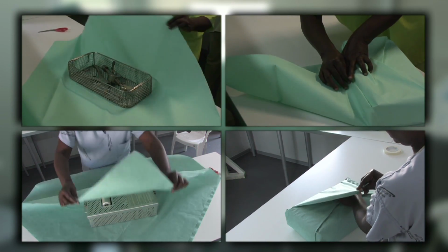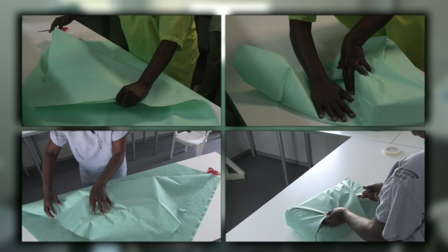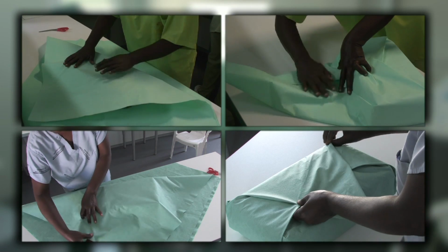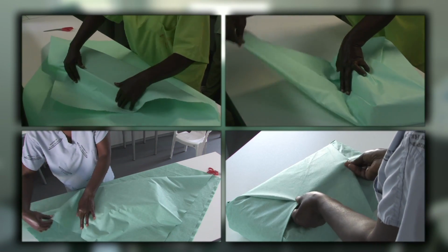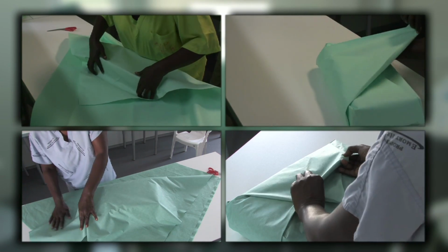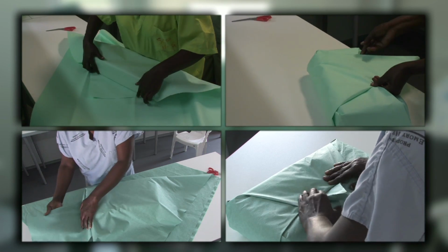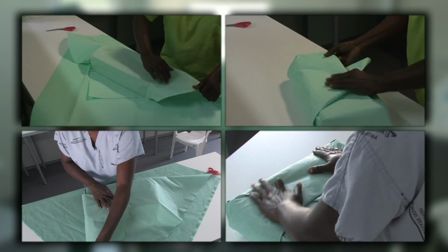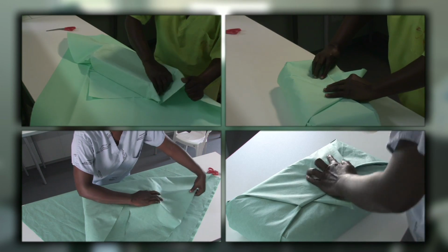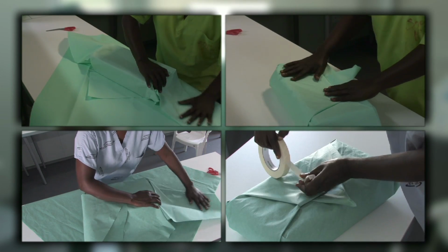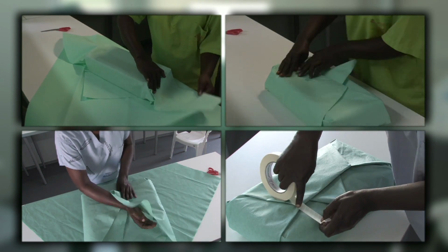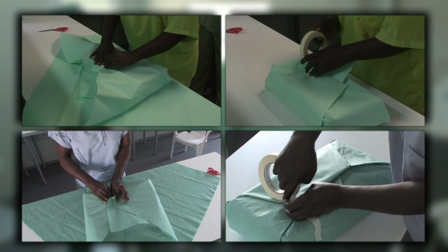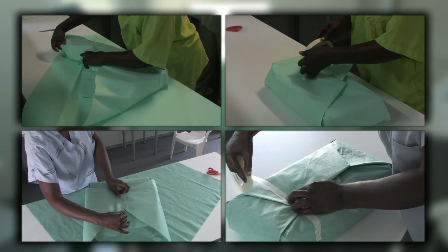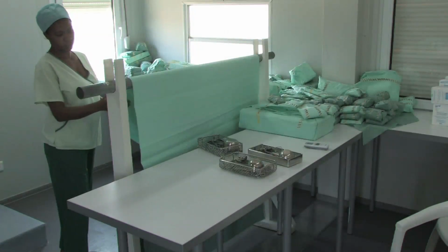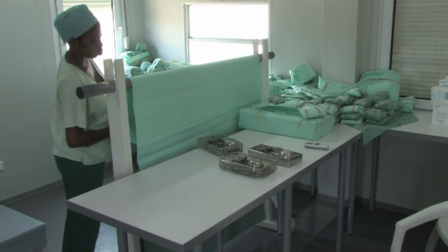A specific folding technique must be used when wrapping baskets or instrument boxes with crepe sterilization paper or non-woven sheets. Envelope folding is the most commonly used technique. The so-called square folding technique is usually used only for packs of linen. It's important to follow the technique exactly, as this makes it possible to open the pack easily at the time of use without loss of sterility.